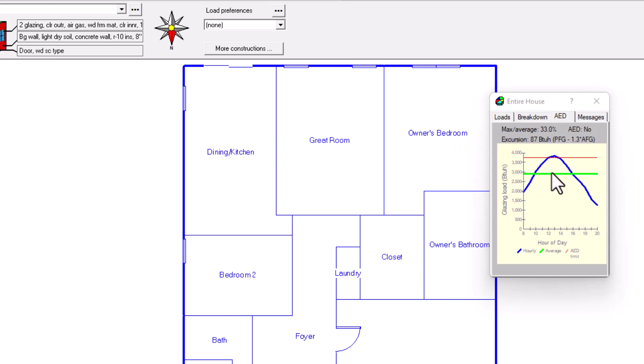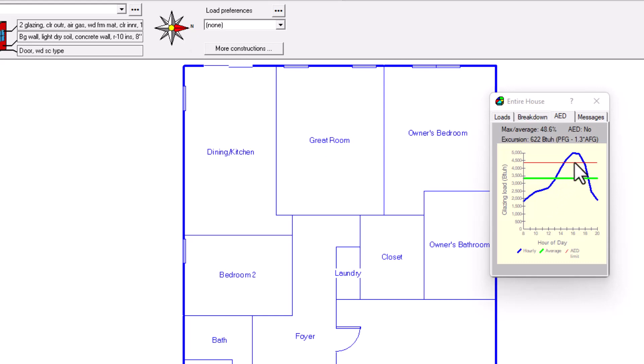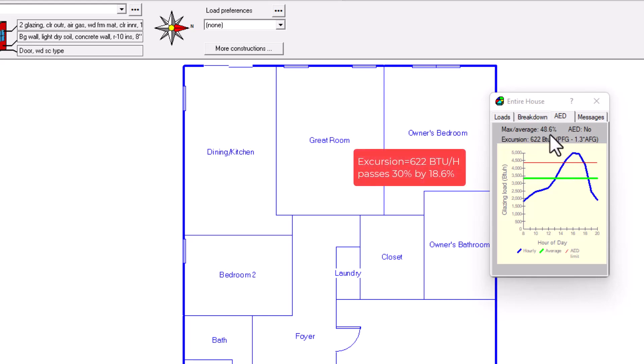For this single-floor house if AED says No, you don't have to zone — you could instead increase the system size by perhaps half a ton. Playing with other orientations: some are even worse, reaching 41.2% excursion, and the worst case reaches 48.6% with an excursion of 622 BTUs per hour — well beyond the 30% limit.